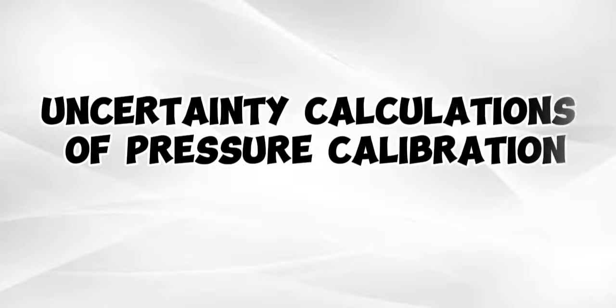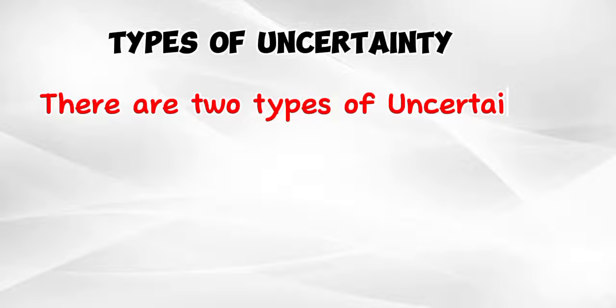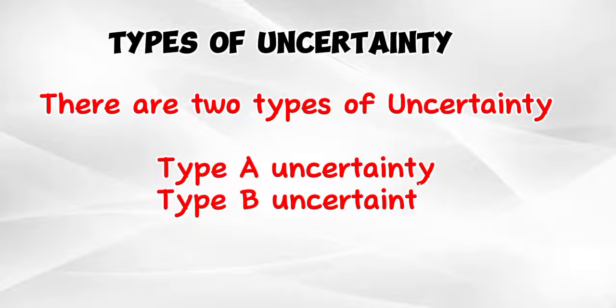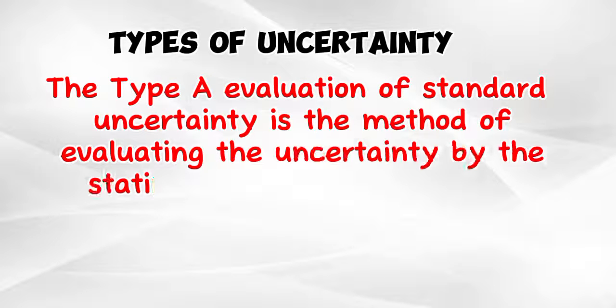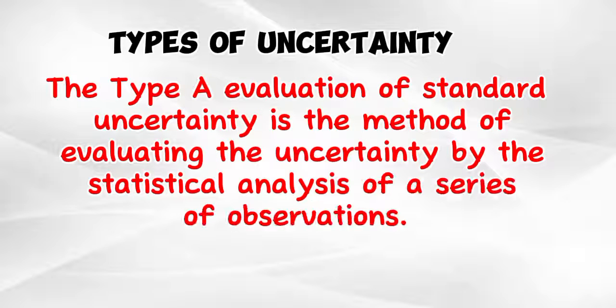Uncertainty Calculations of Pressure Calibration. Types of Uncertainty: There are two types of uncertainty. Type A evaluation of standard uncertainty is the method of evaluating the uncertainty by the statistical analysis of a series of observations.